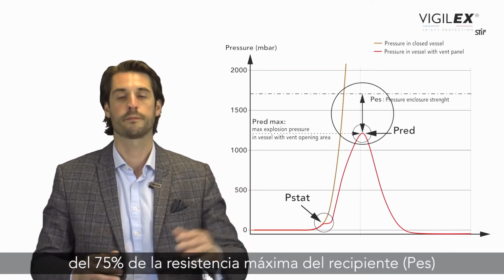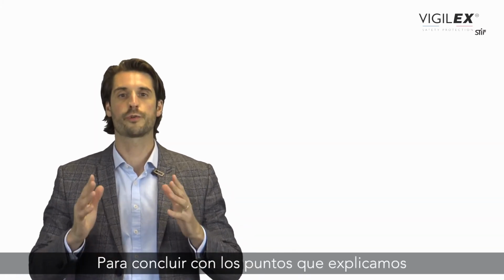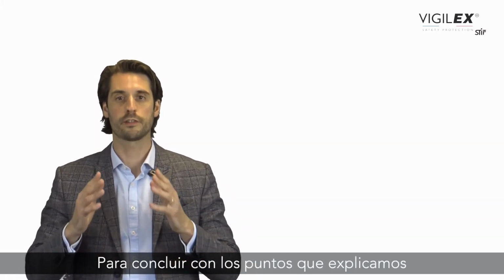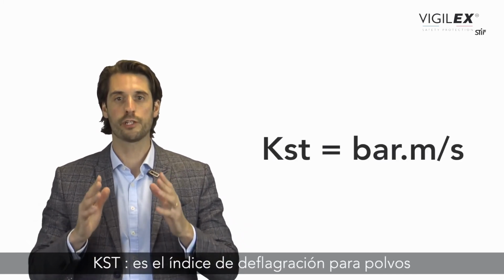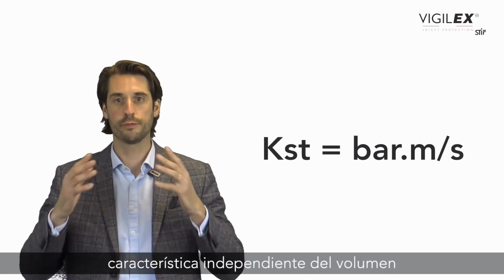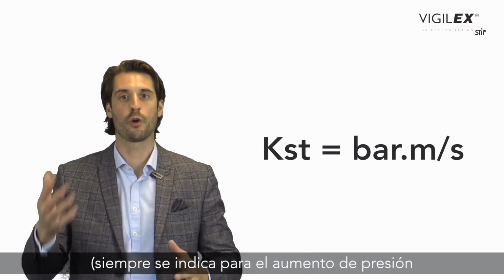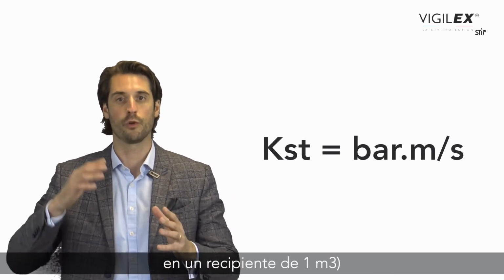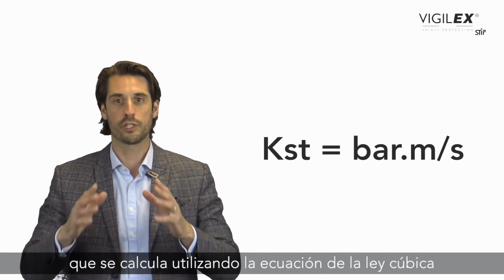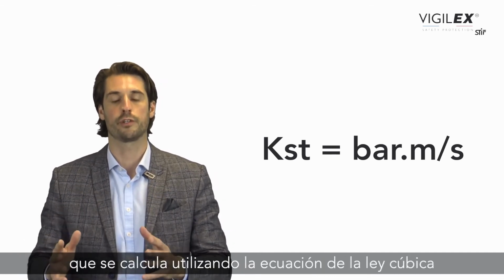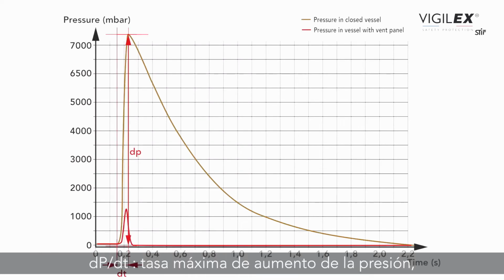the PES. Let's do a short recap of the key points we just described. The KST is the deflagration index for dusts, a volume-independent characteristic. It's always indicated for pressure rise in a 1 cubic meter vessel, which is calculated using the cubic law equation. dP/dt, maximum rate of pressure rise, highest value of the pressure-time curve, measured in a closed vessel during the explosion of a specific mixture.